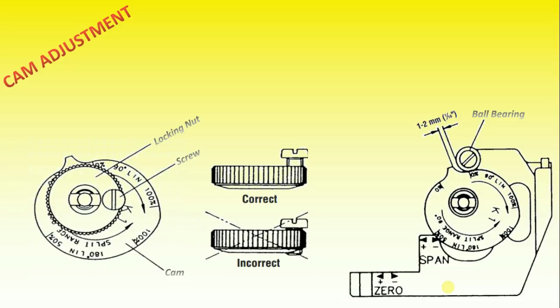To secure the cam, make sure that the screw is backed out from the locking nut. Then finger tighten the locking nut and tighten the screw. Install and adjust the indicator and reinstall the cover.